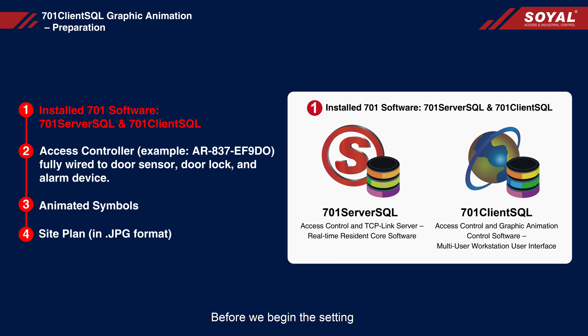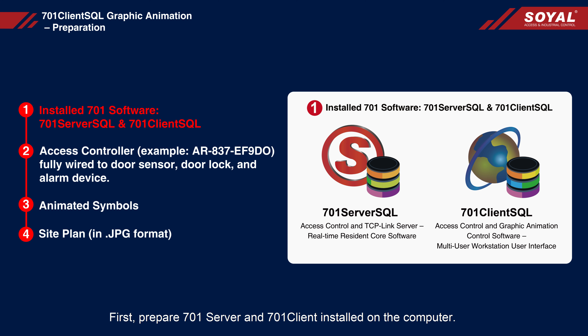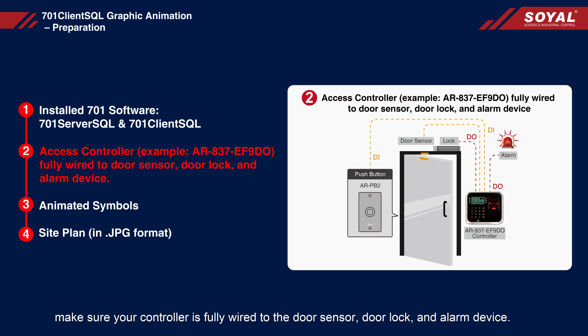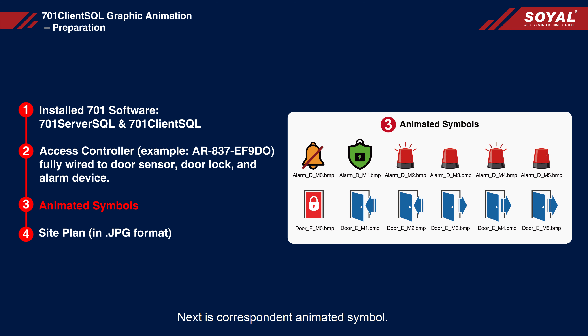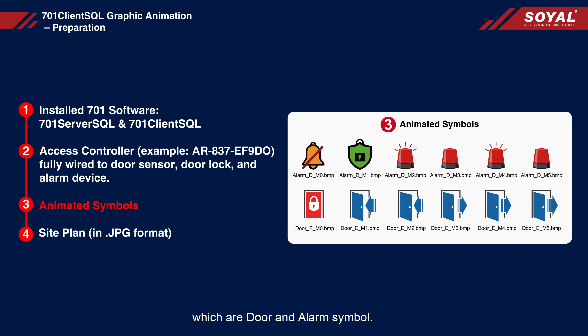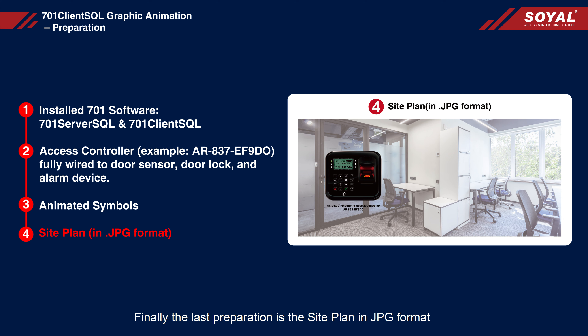Before we begin the setting, there are 4 steps of preparation that need to be done. First, prepare 701 server and 701 client installed on the computer. Second, make sure your controller is fully wired to the door sensor, door lock, and alarm device. In this part, we are going to use the Soyal demo kit to show you the real test. Next, you need the corresponding animated symbols — for each access controller, we need 2 different kinds of symbols, which are door and alarm symbols. Finally, the last preparation is the site plan in JPG format, which is required as the base map for the animated symbol.